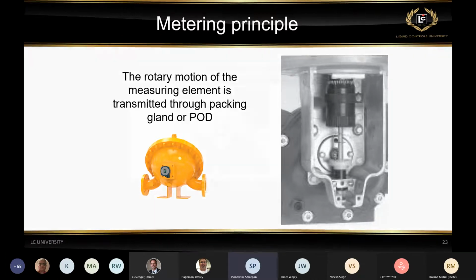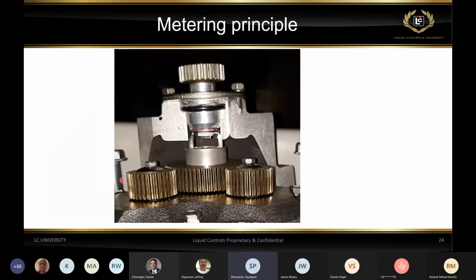Now, this picture might give you a little bit better idea of how that really looks inside. This is a cutaway of one of our smaller meters. This is actually an M5 meter, shown from the bottom. So we have our blocking rotor with a blocking rotor gear and 2 displacement rotors. And you can see the packing gland coming in with a fork drive and engaging directly with the blocking rotor gear. On the other side of that packing gland, we have a gear. So as the blocking rotor turns, the blocking rotor gear turns, engages with the packing gland and ultimately turns the gear that's on the outside of the meter.